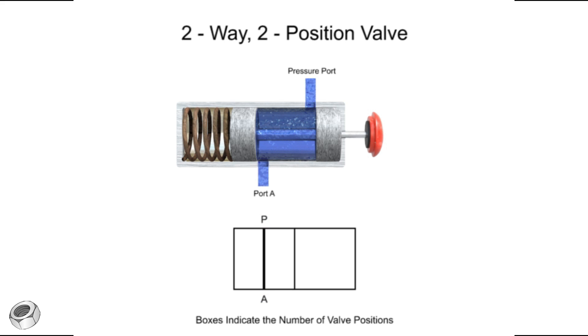The input port is typically labeled P for pressure. Outlet ports are typically given alpha characters starting with A. Other times, the letter stands for the destination of the fluid — for instance, the letter T would indicate a port connected to a tank. This is a fairly simple valve, so port labels are not required.